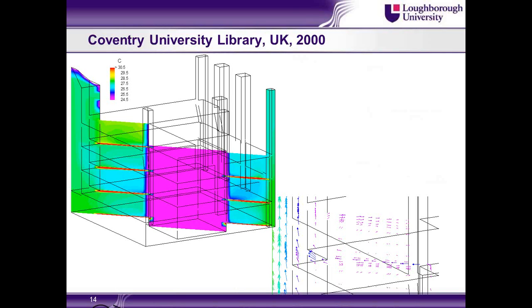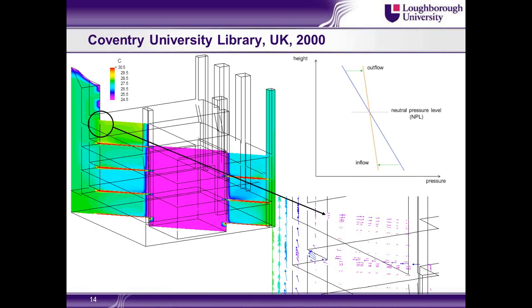We noticed a problem on the top floor here. Hard to see in this light, but that's slightly warmer than the lower floors. If we look a bit closer at that, we can see that in fact there is backflow from the central light well onto the top floor, and that is an example of what can happen if you get the opening sizing wrong, or if there is insufficient height above the uppermost opening, such that the neutral pressure level, that's this point here, falls below this opening. And that's what's happened here.